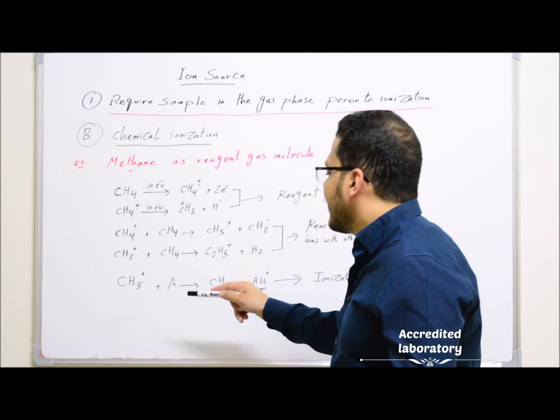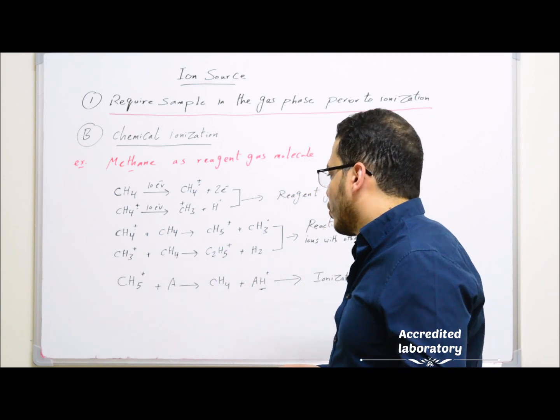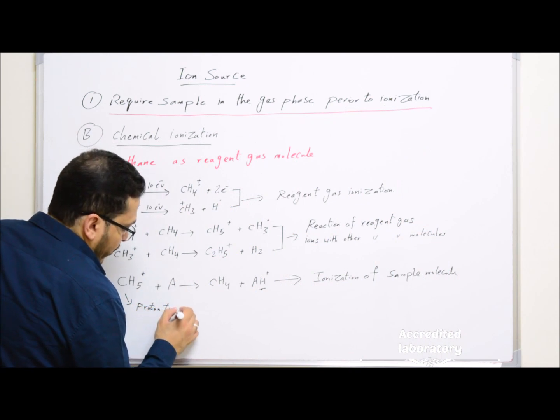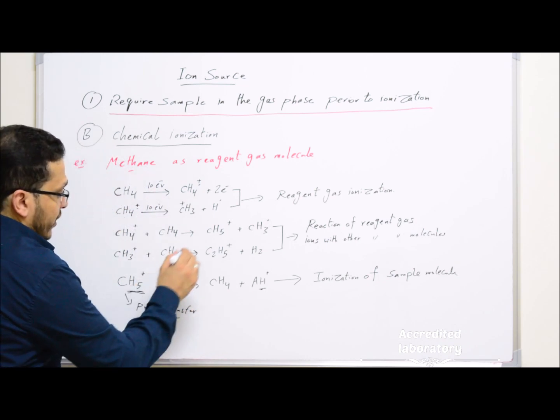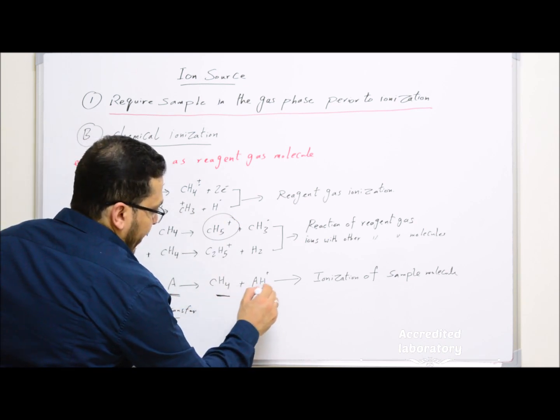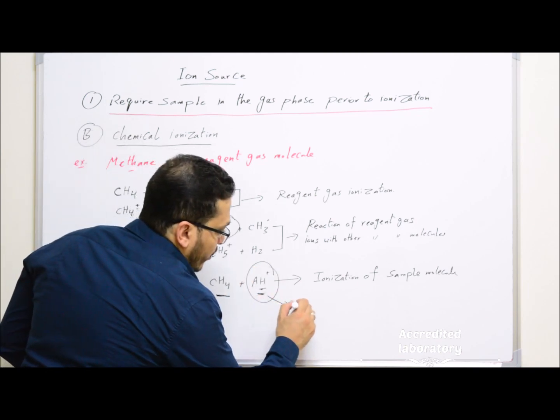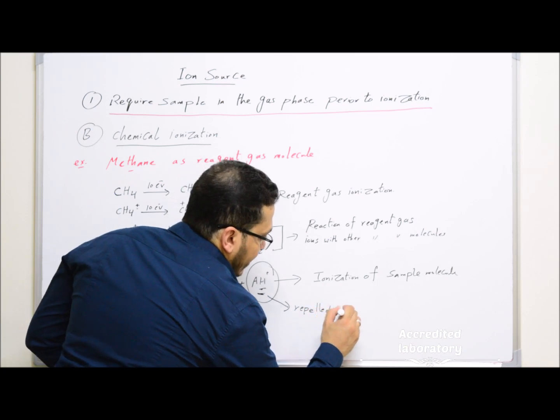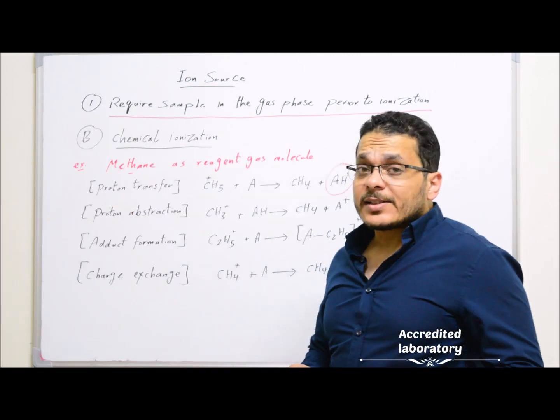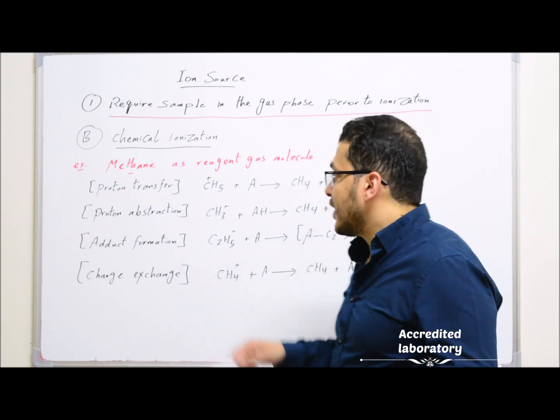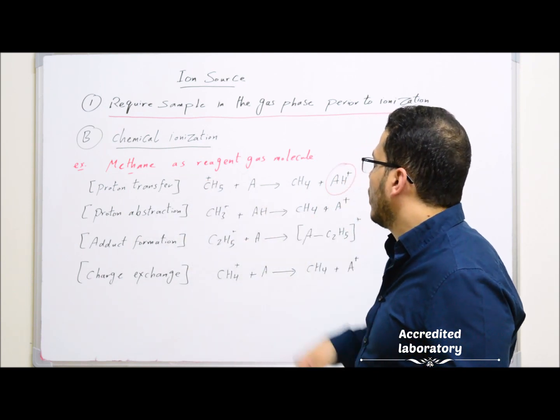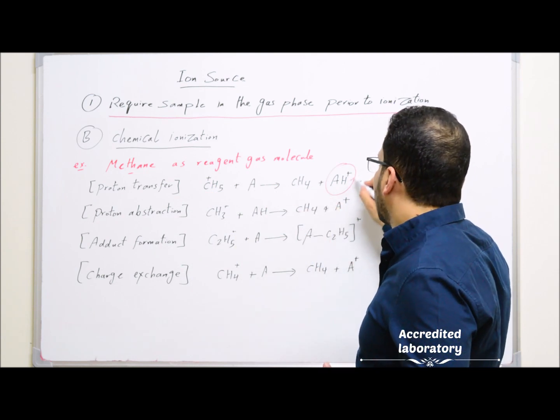These reagent gas ions then react with sample molecules to ionize them. In the case of proton transfer: CH5⁺ (the reagent gas ion) reacts with sample molecule A to form CH4 plus AH⁺. The ionized sample molecule AH⁺ will be sent as it is to the mass analyzer and will not be fragmented again. In proton transfer, a proton is transferred from the reagent gas ion to the sample molecule to form CH4 plus AH⁺, which is the ionized sample molecule.